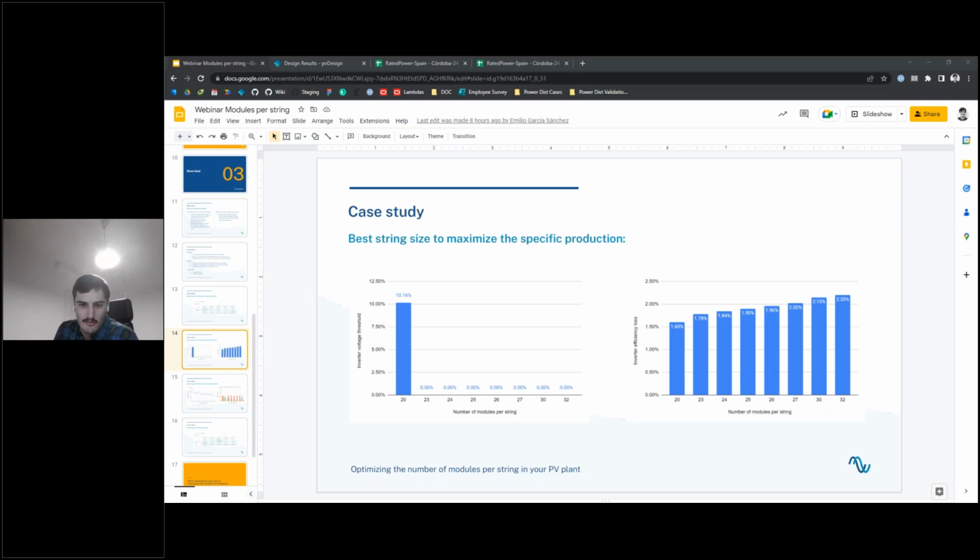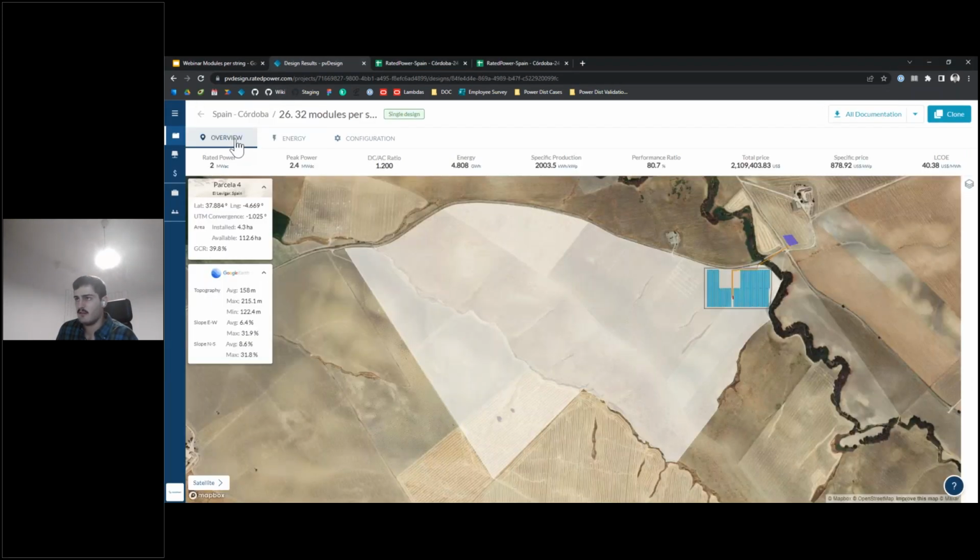Okay, so Srikan, sorry if I do not pronounce the name well, was asking about the DC line losses that can lead effectively to a voltage drop before reaching the inverter, especially with virtual central design using string inverters, and if it can be considered when calculating the string length with pvDesign. So the answer is yes.